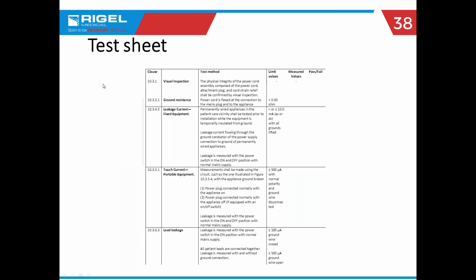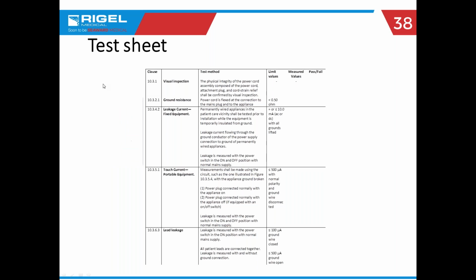So basically, this is a test sheet that you're going to need at the end of the testing. This can be captured by you manually, or by the safety analyzer if it has that capacity. So basically just pass/fail on the visual inspection, ground resistance, leakage current, and lead leakage current, and you're all set. Pretty basic.